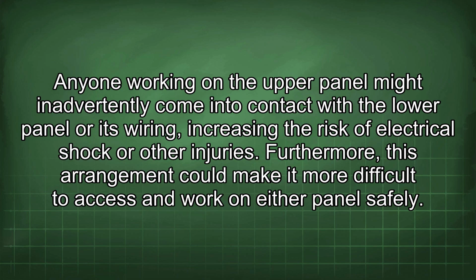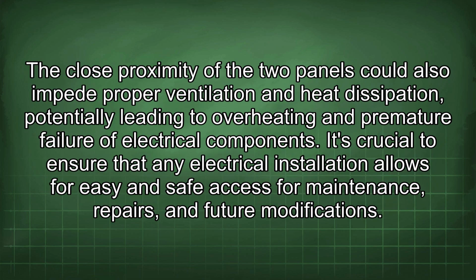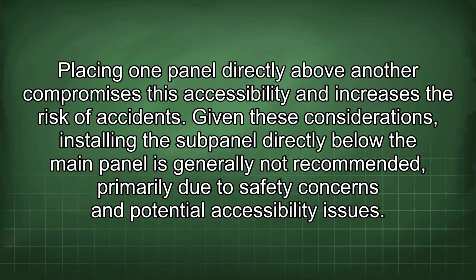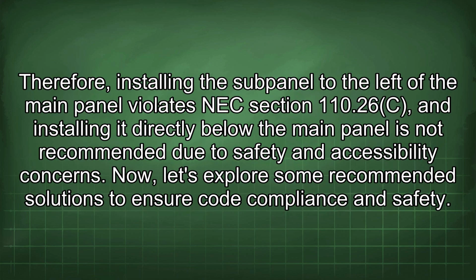Furthermore, this arrangement could make it more difficult to access and work on either panel safely. The close proximity of the two panels could also impede proper ventilation and heat dissipation, potentially leading to overheating and premature failure of electrical components. It's crucial to ensure that any electrical installation allows for easy and safe access for maintenance, repairs, and future modifications. Placing one panel directly above another compromises this accessibility and increases the risk of accidents. Given these considerations, installing the subpanel directly below the main panel is generally not recommended, primarily due to safety concerns and potential accessibility issues. Therefore, installing the subpanel to the left of the main panel violates NEC Section 110.26(C), and installing it directly below the main panel is not recommended due to safety and accessibility concerns.